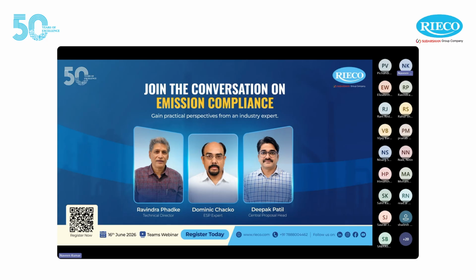And the third one, of course, is our topic of interest, which is how to treat these emissions or how to treat these contaminants. So we know that we have essentially two types. One is the particulates, for which we have systems based on equipment like cyclone separators, which can give you a removal efficiency of 70% right up to 95-96%. Then we have bag filters, pulse jet cleaning, which can give us an efficiency of more than 99%.